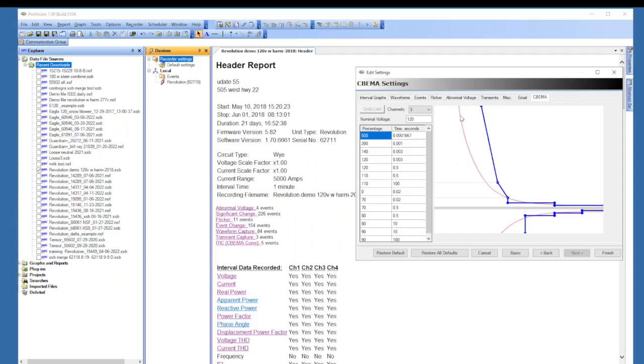There's actually 2 curves here. The CBEMA curve is the orange curve, and the blue is an updated ITIC, Information Technology Industry Council, set that up. These came from computer companies, and they wanted to see a 1-page graph with events that could affect their switch power supplies. So basically, any events which are going to be circles or triangles on this graph, if they're inside these curves, then they're acceptable and they won't affect computer servers. But if those events are in the upper right, then it could damage power supplies, switch power supplies, that kind of thing. And if they're in the lower right, then it could slow down a production line, slow down a motor.